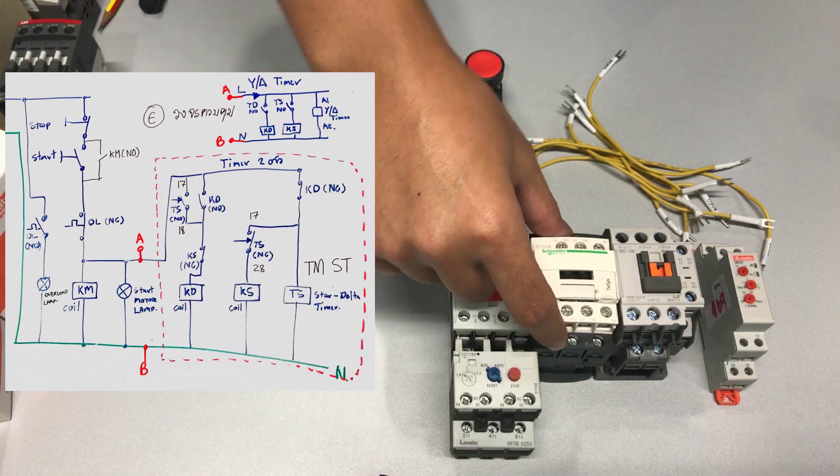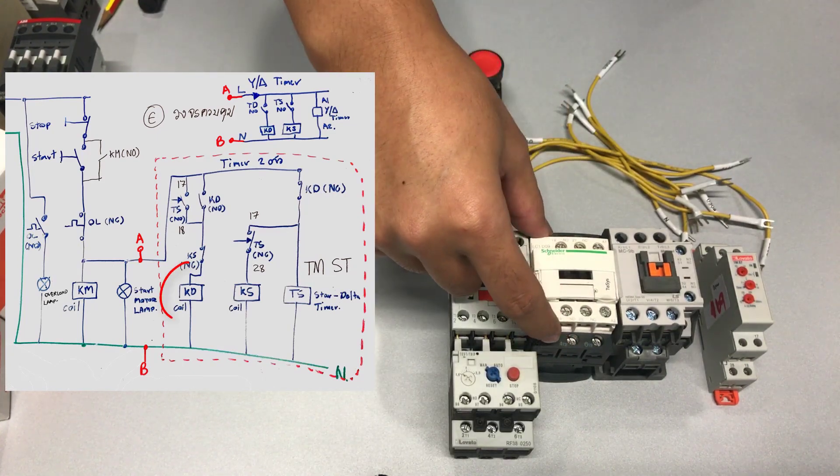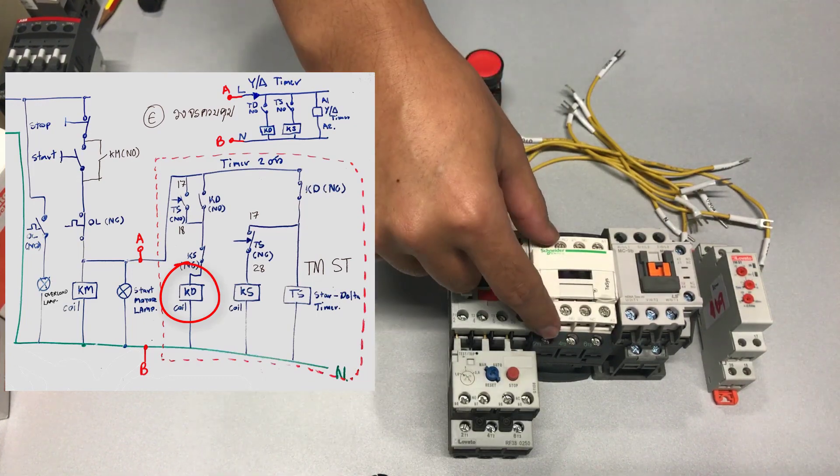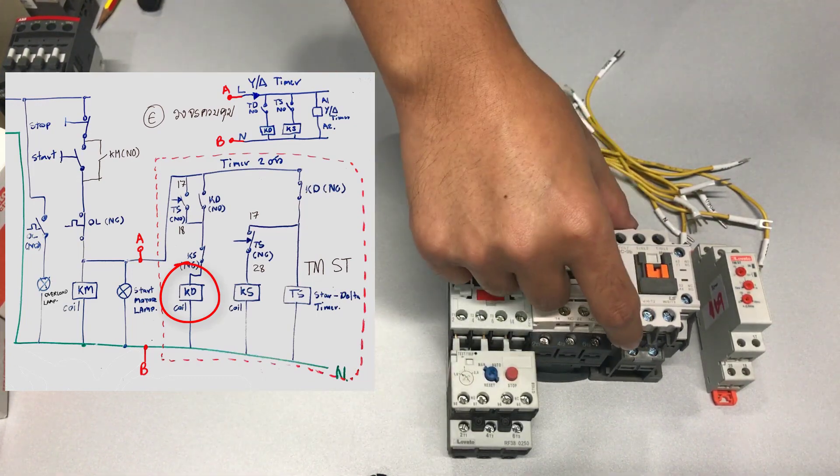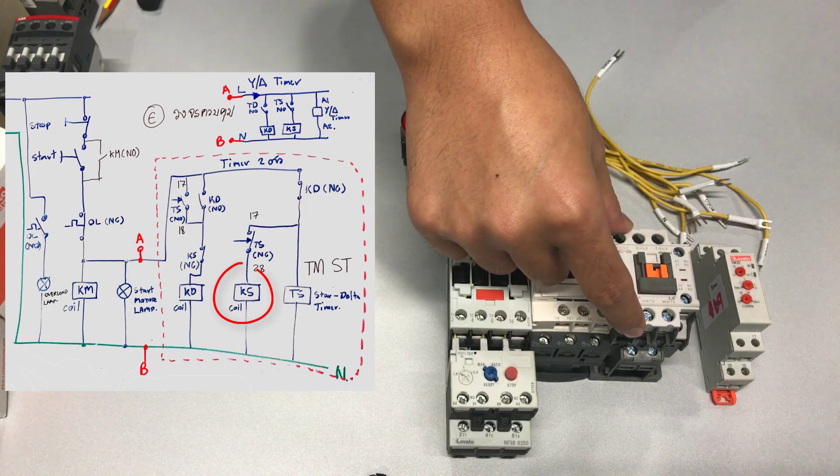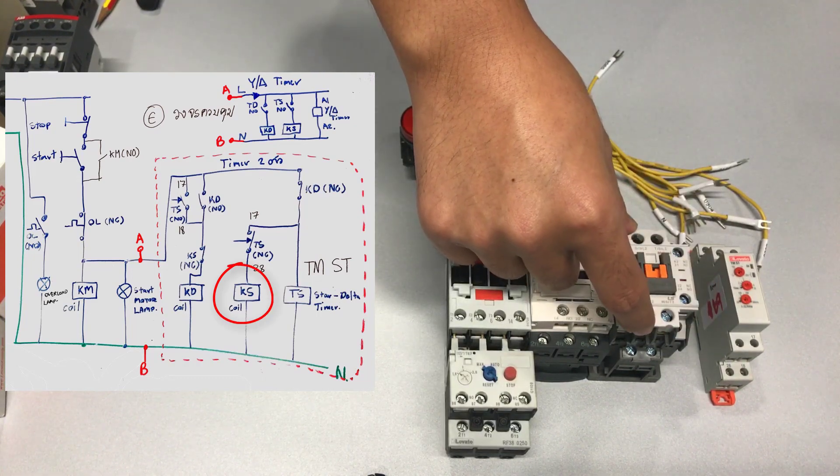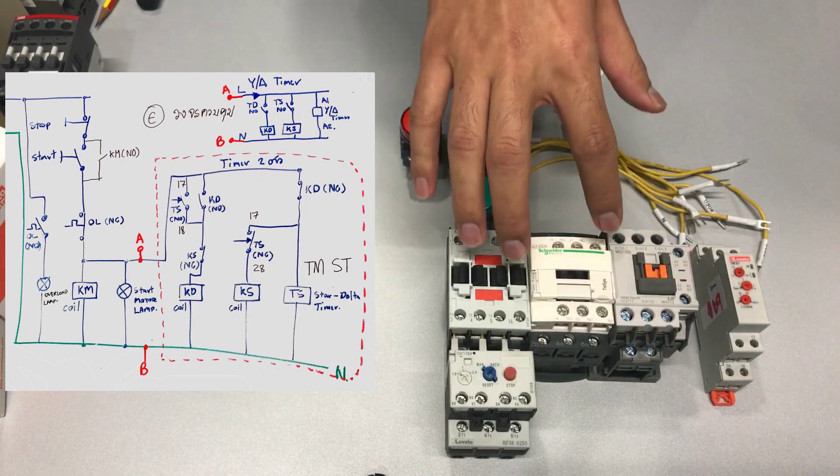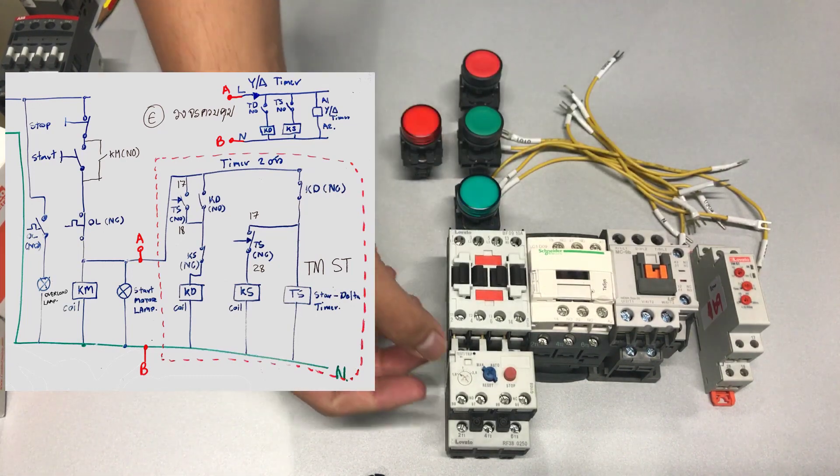The second one is the delta contactor labeled KD. This one you will need the auxiliary contact to have both NO and NC. The third is the star contactor labeled KS. This will also need the auxiliary contact to have both NO and NC. The three of them can be of the same size.